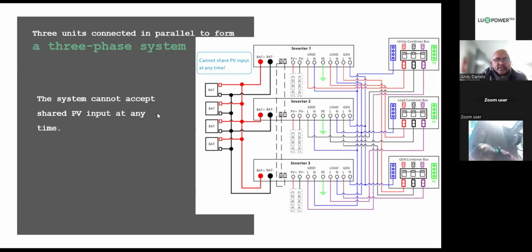Levan, okay, he's been answered. I think we've missed it, but is the smart load function available on the SNA 5000 with the latest firmware? Not yet. The reason why the smart load function is not available yet is because the topology of the older version of the 5 kilowatt differs a little bit in that it doesn't have a CT on the Gen port, which for us is critical. So the old SNA won't have this feature. The SNA 6 will be a better option. That's correct. Thank you, Mau.